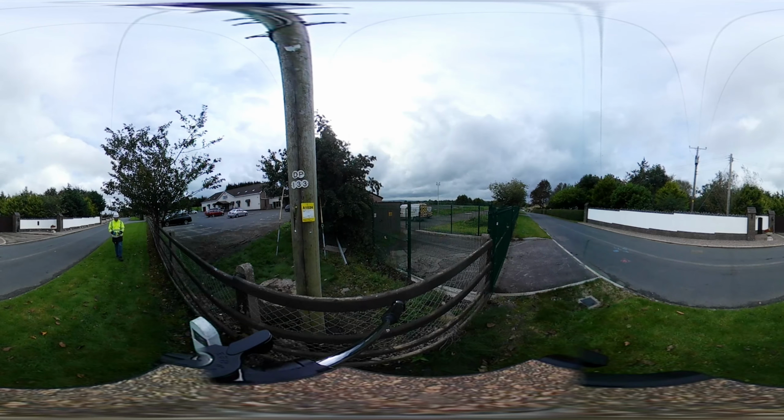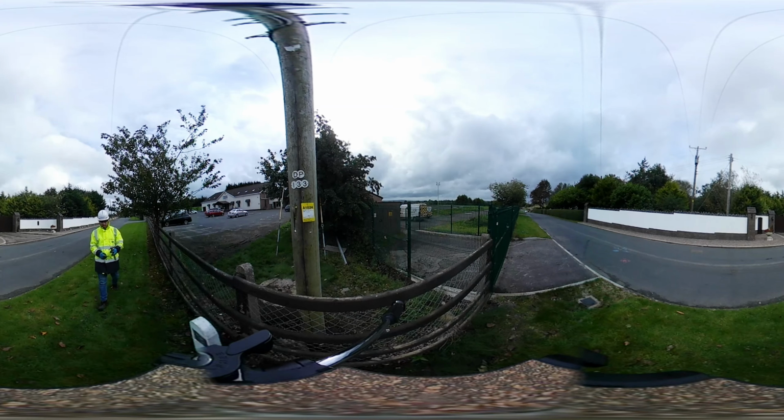The risk assessment form will calculate these distances automatically and give you one of 3 potential answers. If the distance is less than 1.8 metres, intervention from the local DNO will be required, and this usually requires a shutdown. If the distance is between 1.8 and 3 metres, the controlled access procedure will apply. If the distance is greater than 3 metres, normal working procedures apply.